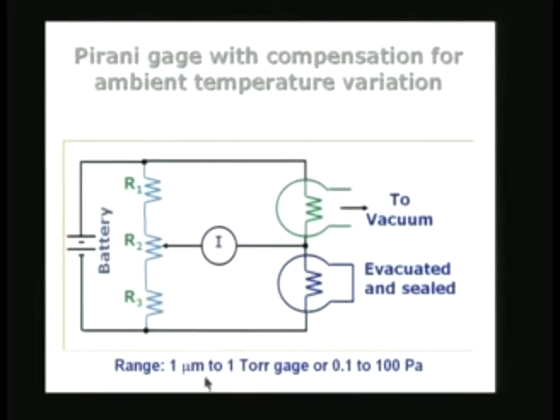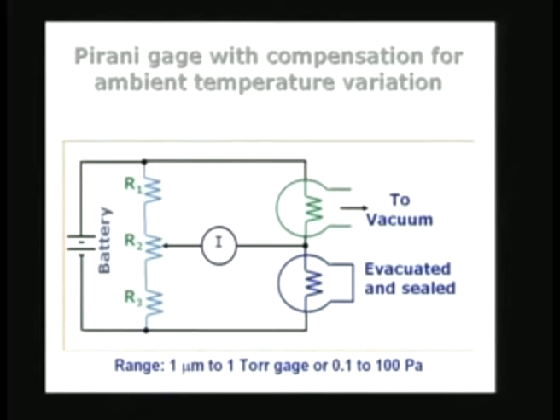The range of the Pirani gauge is from 1 micrometer pressure — that is 10⁻³ millimetres of mercury — to 1 millimetre of mercury, or 0.1 to 100 Pascals. The Pirani gauge is usually used with the rough vacuum pump. When the rough vacuum pump reduces pressure to a value somewhere in this range — from 100 Pascals to about 0.1 Pascals — we can use the Pirani gauge. If the vacuum pressure is even lower, that is higher vacuum, a different type of gauge is needed.